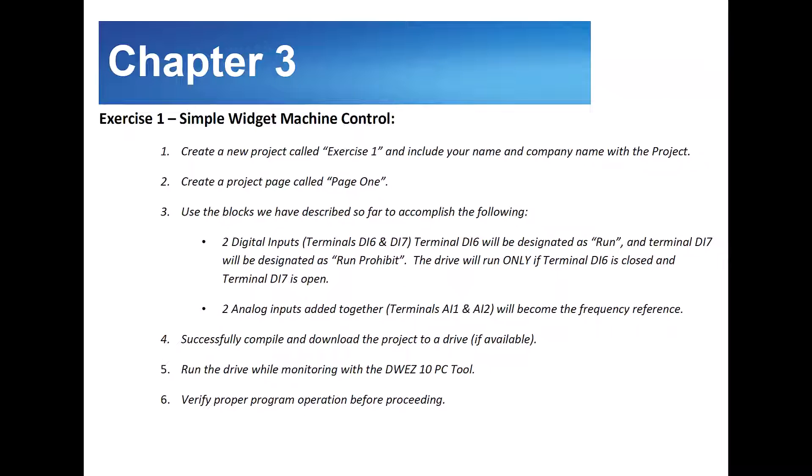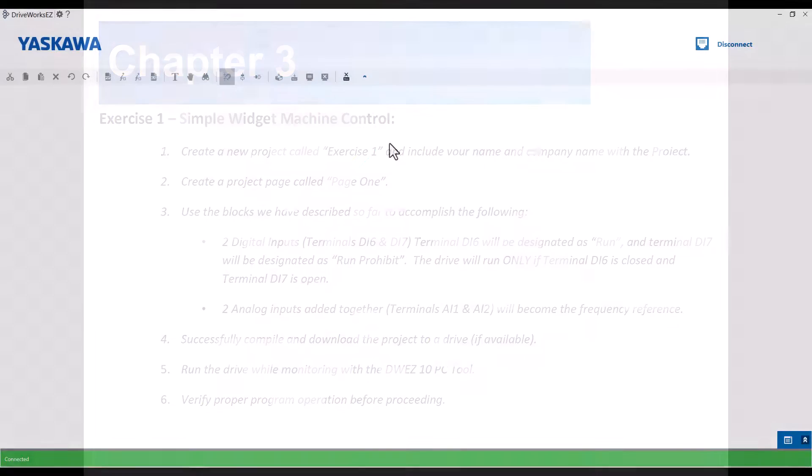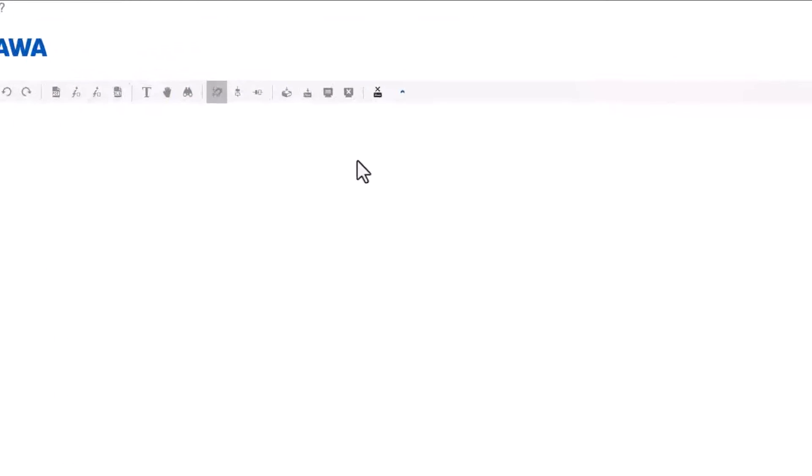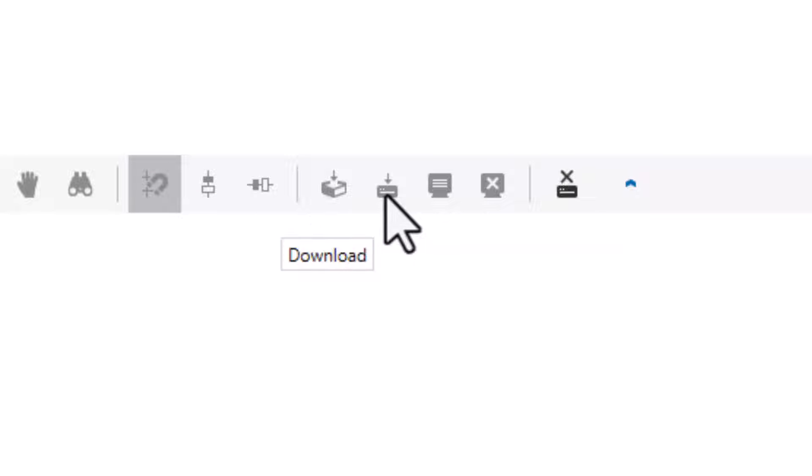Second step will be two analog inputs added together. We'll use AI1 and AI2, which will become our frequency reference. We'll have to make sure that AI2 is changed from 4 to 20 milliamps to 0 to 10 volts DC. After we create our program, we'll have to successfully compile the program and download it to our drive if we have one.